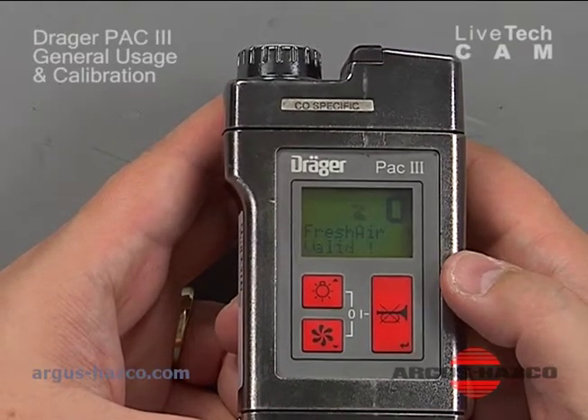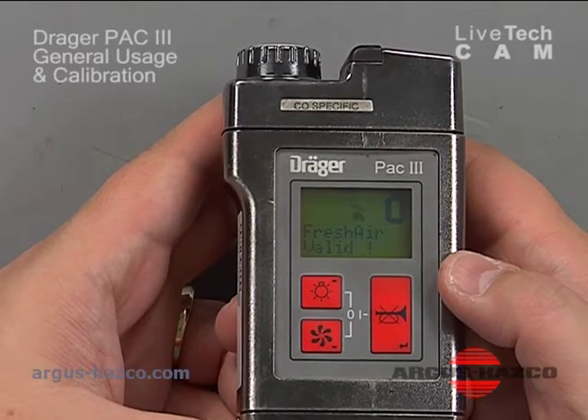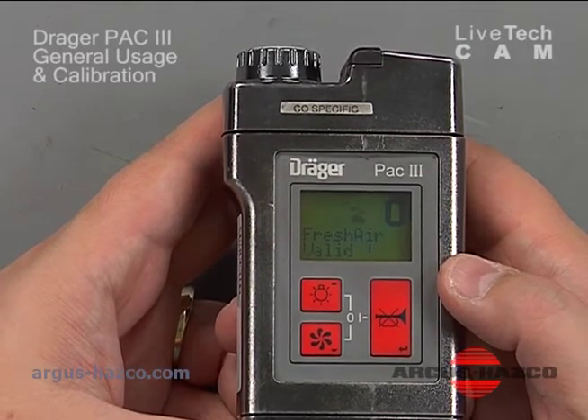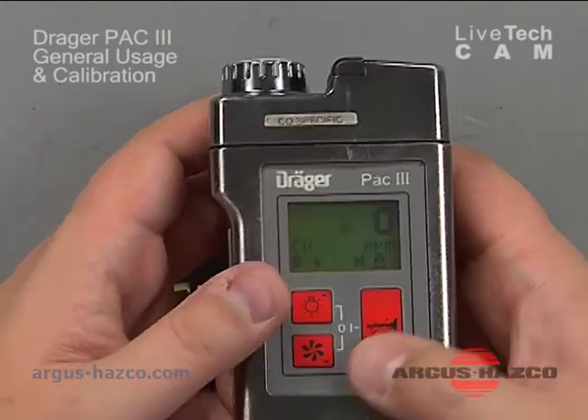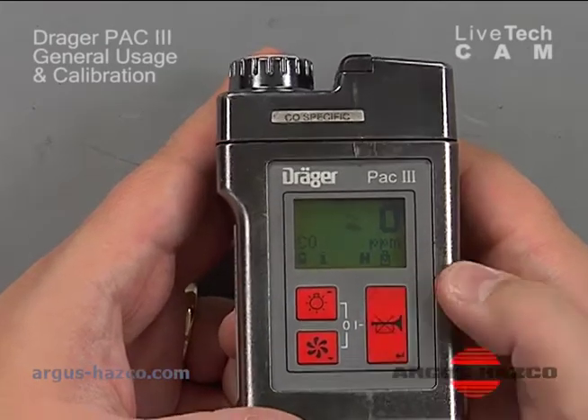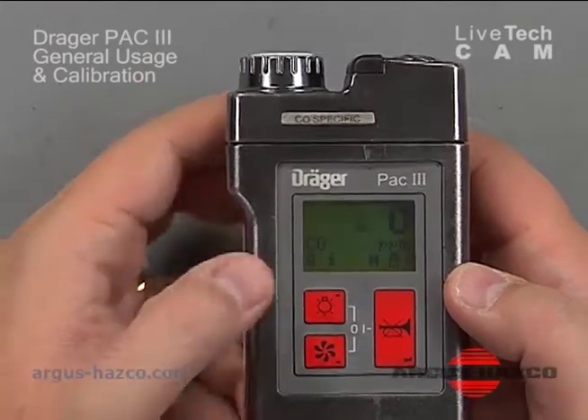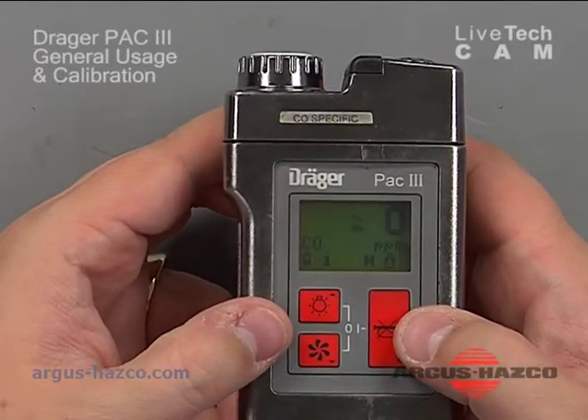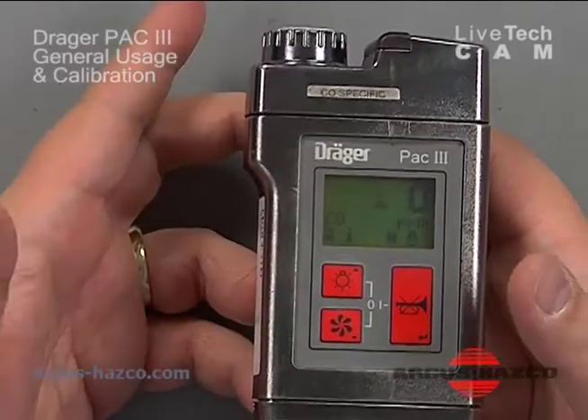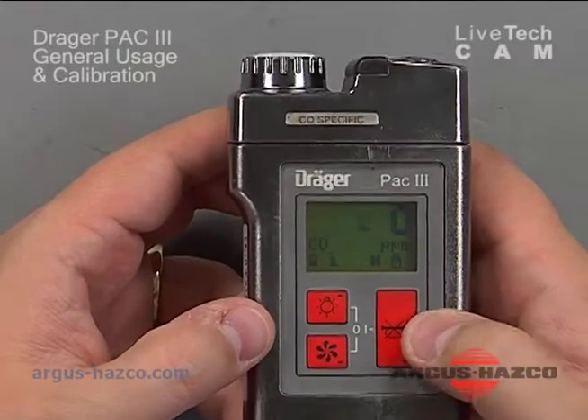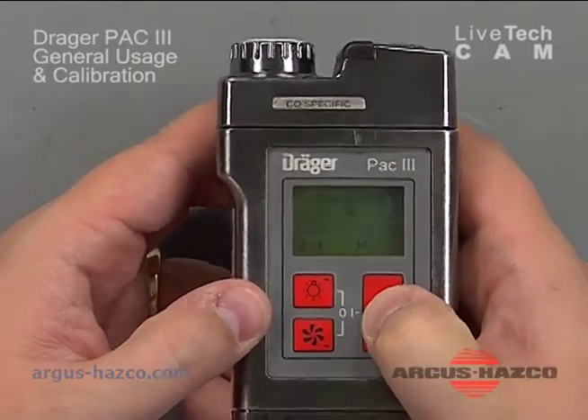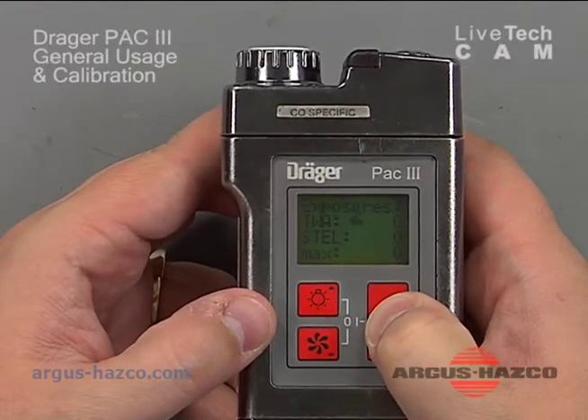It says wait, valid. So that becomes very useful when you have to zero this every single day before use, other than having to go through this calibration menu to get to it. And fresh air zero should be done to give a baseline zero so the sensor knows what fresh air is in comparison to the target gas we're going to use for calibration. So we press and hold this button again to get to calibrate.